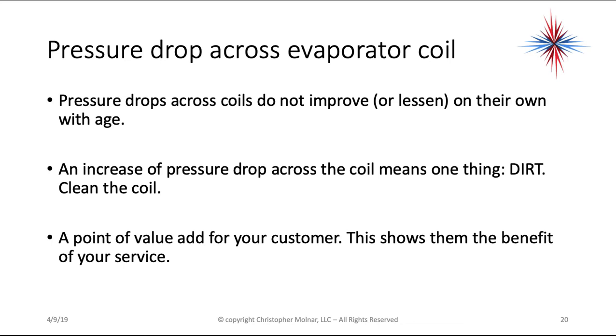Pressure drops across evaporator coils and filters actually affect temperature difference. So if you're taking a temperature difference reading, it could be affected by the cleanliness of your evaporator coil and filters. The more pressure drop, the slower the air will move. The longer it sits on a coil, the more your temperature split is going to increase.